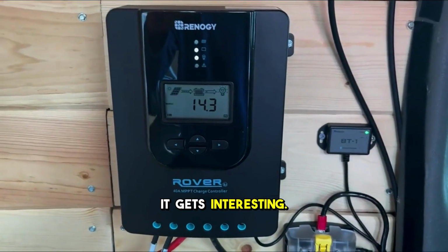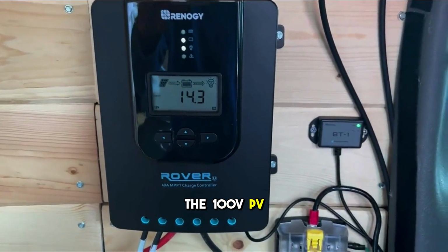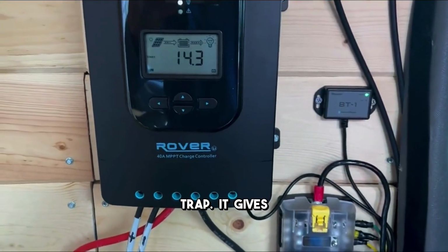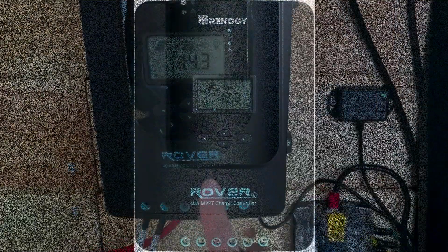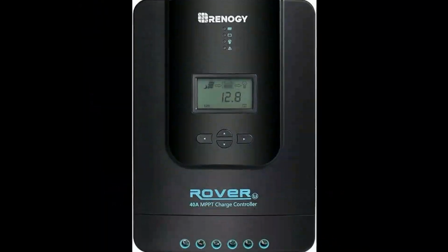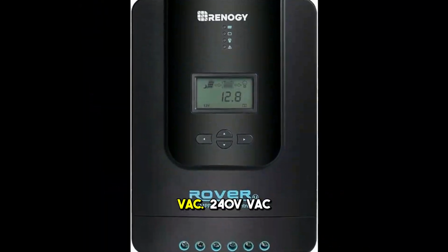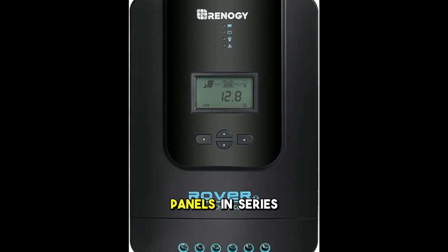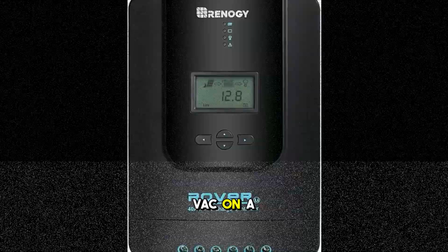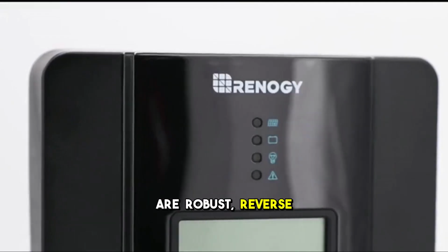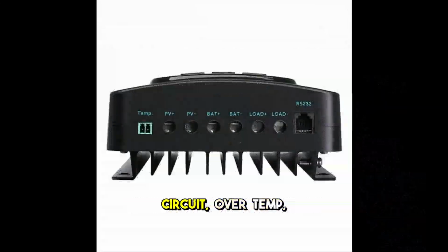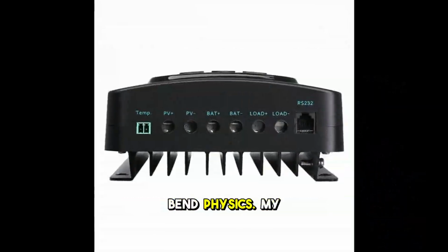But here's where it gets interesting. The 100V PV limit is a gift and a trap. It gives you wiring flexibility, series strings reduce copper loss, but you must calculate cold weather VOC. Two 40V VOC panels in series can hit low 90s VOC on a freezing morning. That's fine. 3 in series could exceed 100V and toast your day. The Rover's protections are robust: reverse polarity, overcharge, short circuit, overtemp, but they can't bend physics.